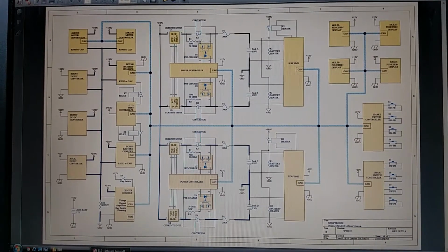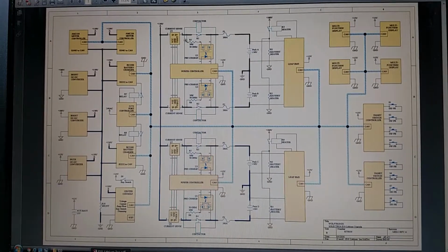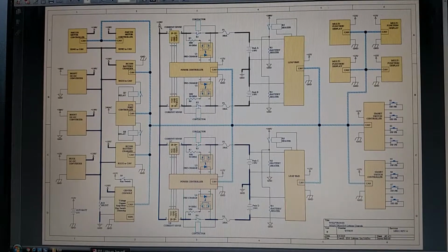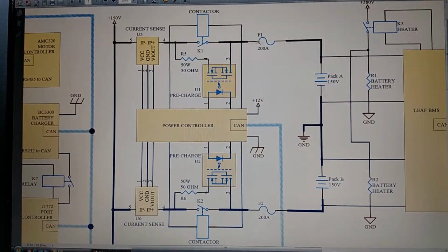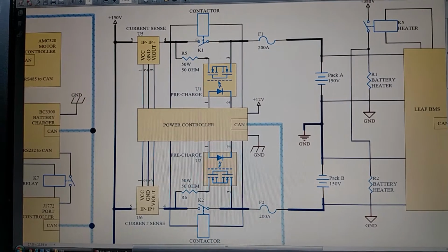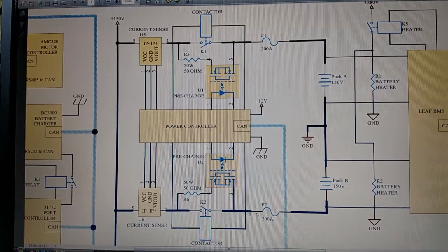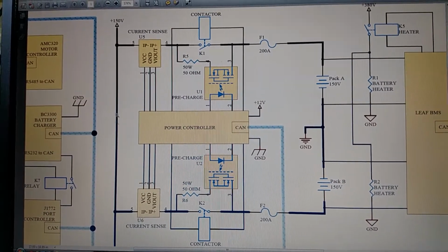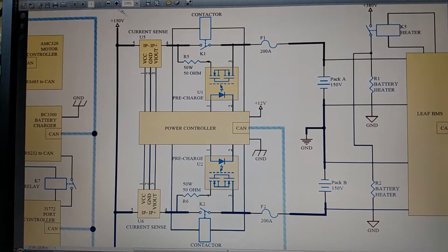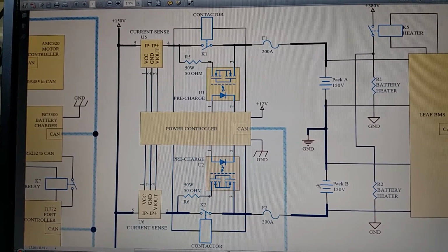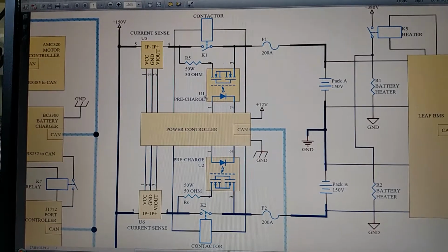And with that information, we can now use that. The power controller now knows the voltage of this stack, and with the voltage here, it knows the voltage on either side, so it can determine if it needs the pre-charge, or can turn on these contactors. Since it knows essentially the voltage of this bus, the voltage of this bus, and the voltage of this bus, it can make its decisions based on that.